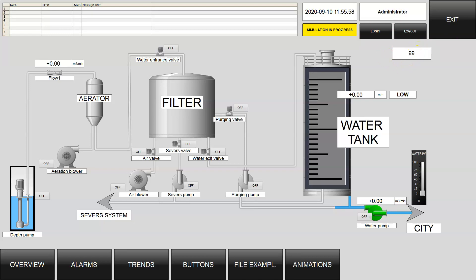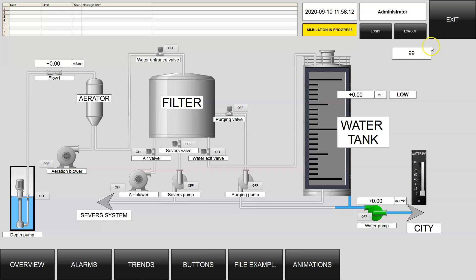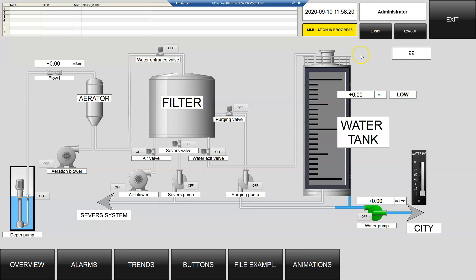Anyway, this kind of situation you can use directly from your PLC. So you have the tag inside your PLC, and you can write the value into the tag in WinCC Runtime, and you can manage whether a user is logged on or not.